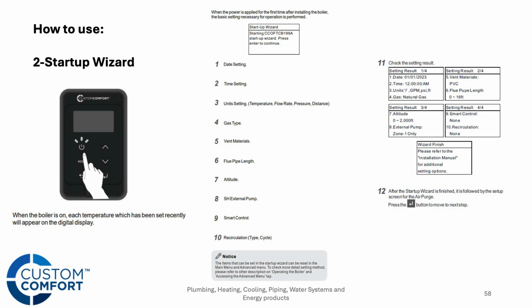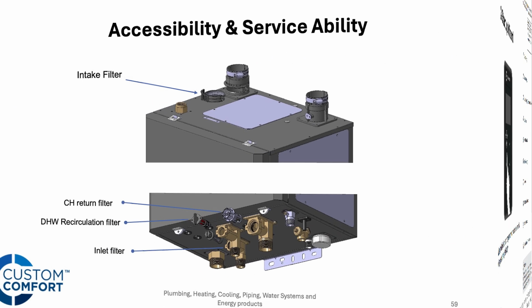You're going to tell it whether it's natural gas or propane. You're going to tell it how long the vent length is. You're going to tell it what the vent material is. So again, a little bit different than the dip switches we talked about earlier. This is all done in that Startup Wizard, right? So what are you venting it with and how far are you venting it? And then the fan and the control and the boiler are going to do the rest from there. Altitude, I would say for the majority of the applications that we run into, that's not going to be a factor, right? But yeah, super easy with the Startup Wizard. Again, it's going to walk you through everything you need to know in checking out that boiler.